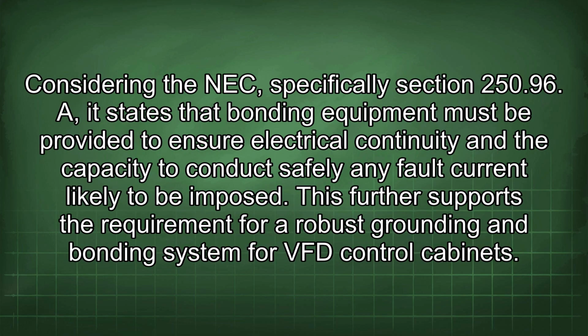Considering the NEC, specifically section 250.96(A), it states that bonding equipment must be provided to ensure electrical continuity and the capacity to conduct safely any fault current likely to be imposed. This further supports the requirement for a robust grounding and bonding system for VFD control cabinets.